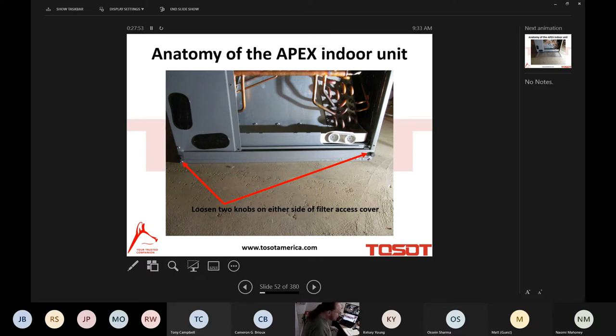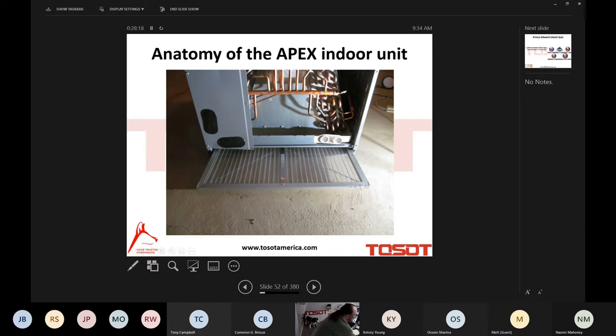The larger one, and this is why this one's always in my consciousness, is what we have in the house here. And it takes a 20 by 23 filter. I'm getting a little ahead of myself. To gain access to the filter, you simply undo these two little twisty knobs at the bottom of the fan coil unit, and this cover is removable, and that will gain you access to the factory supplied permanent filter. Now, I think most of you guys will agree with me that you and your customers don't like factory supplied permanent washable filters.